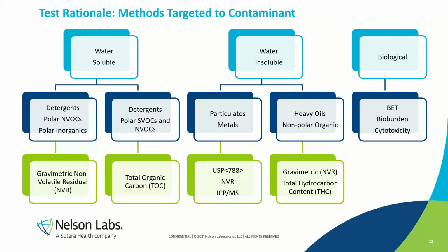And then you can use a method, either gravimetric or THC, total hydrocarbon. Total hydrocarbon is kind of the other side of the coin to TOC. We would extract in hexane and then pull an aliquot and put that on a GC-FID to give a quantitative amount of non-polar organic carbon. This is great for all metal devices. Hexane is compatible with metal and THC has a nice sensitivity. It's also listed in ISO 19227.